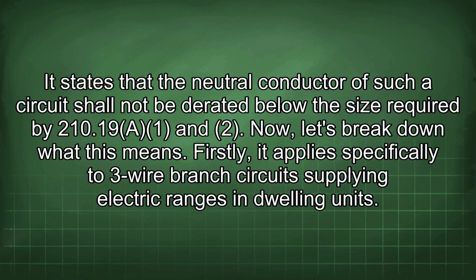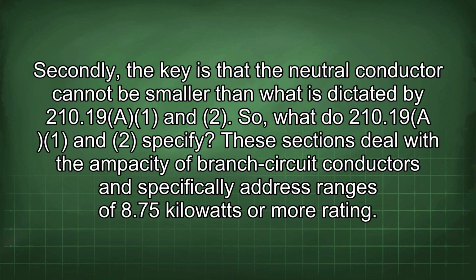Firstly, it applies specifically to 3-wire branch circuits supplying electric ranges in dwelling units. Secondly, the key is that the neutral conductor cannot be smaller than what is dictated by 210.19(A)(1) and (2). So, what do 210.19(A)(1) and (2) specify? These sections deal with the ampacity of branch circuit conductors and specifically address ranges of 8.75 kilowatts or more rating.